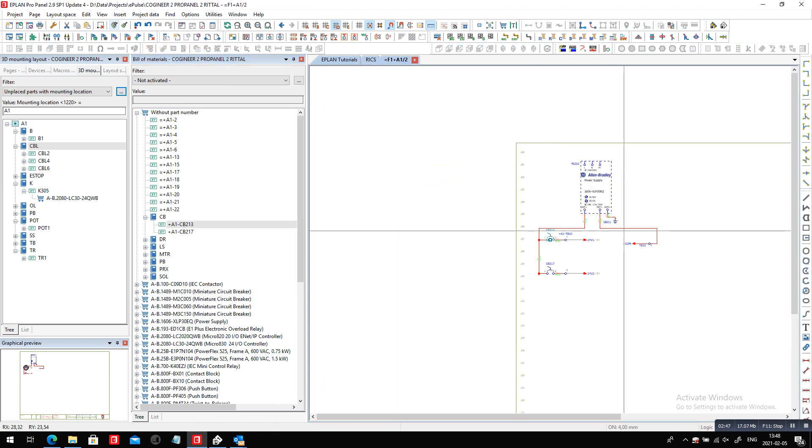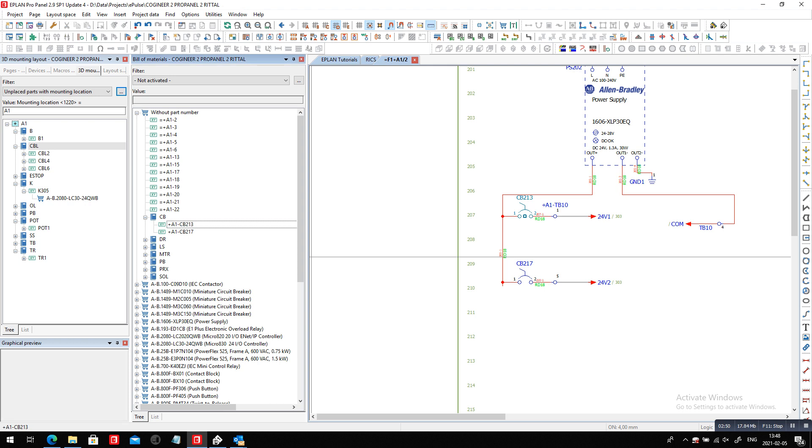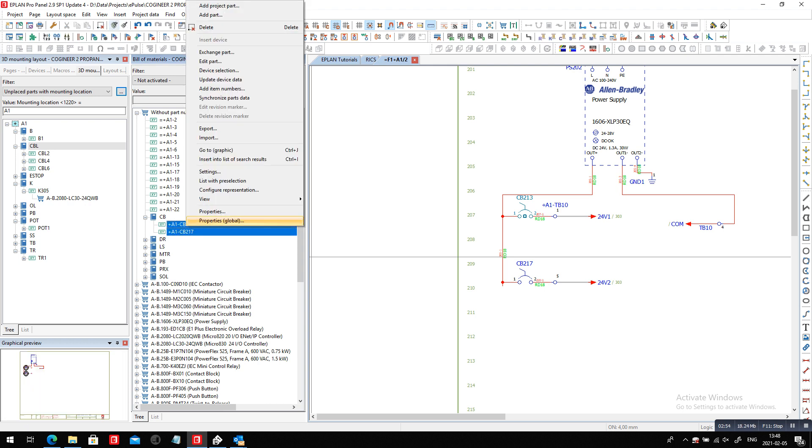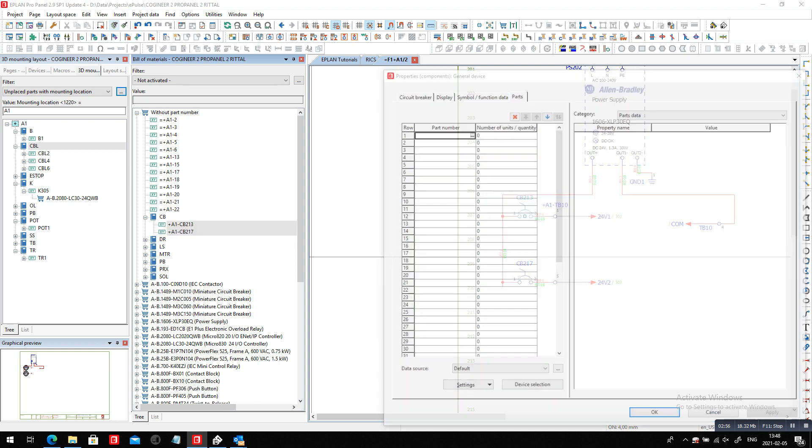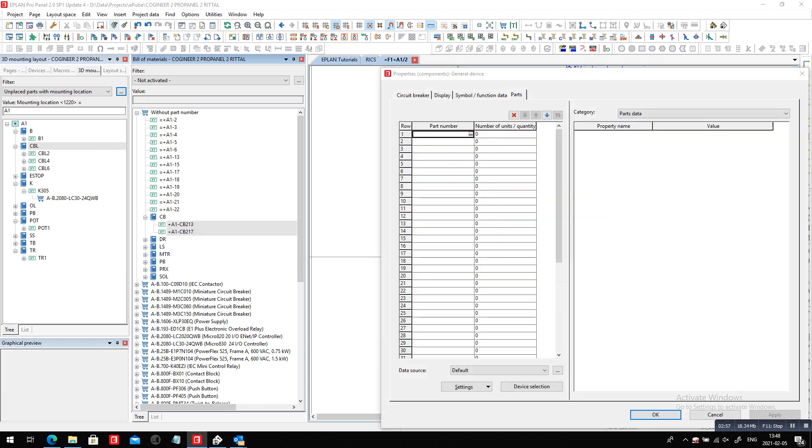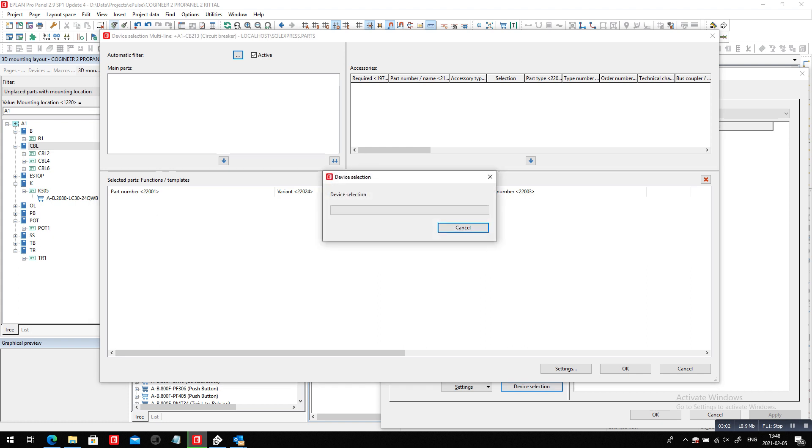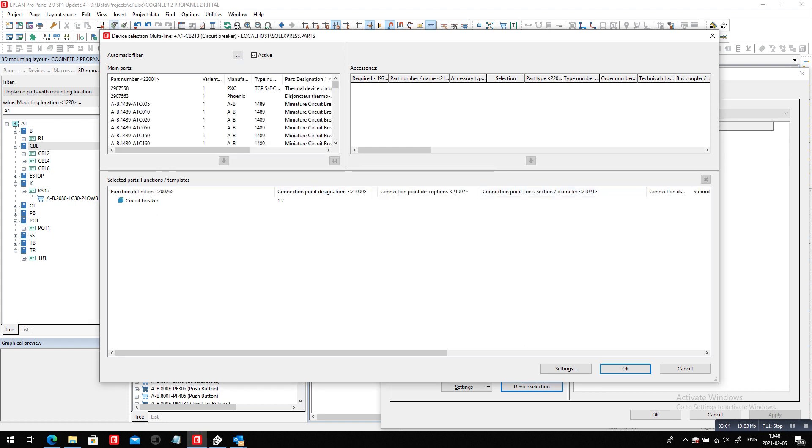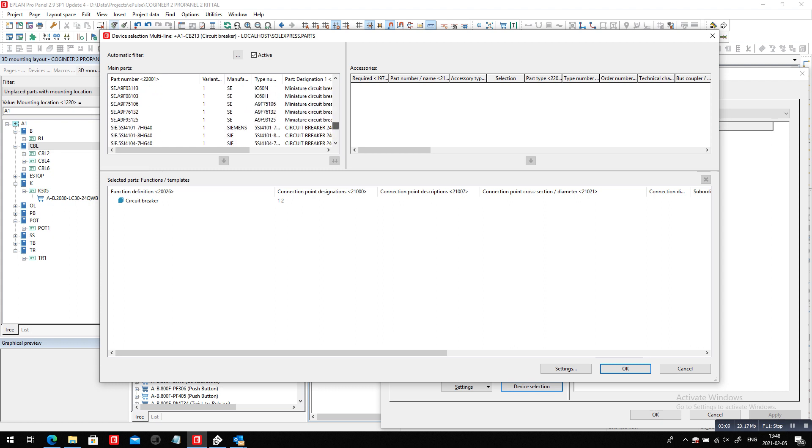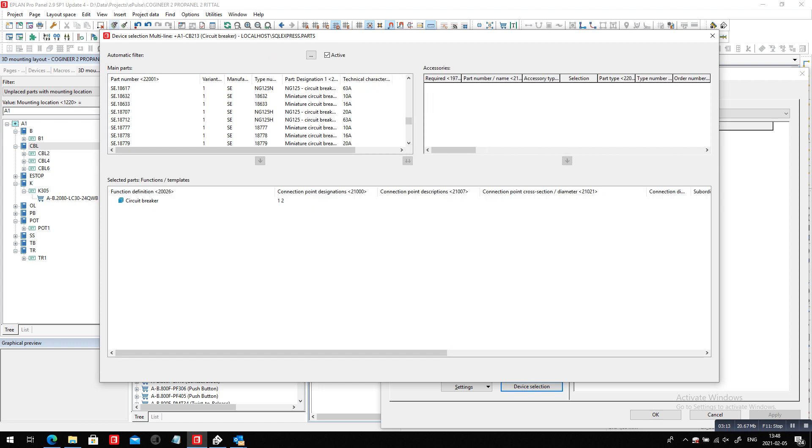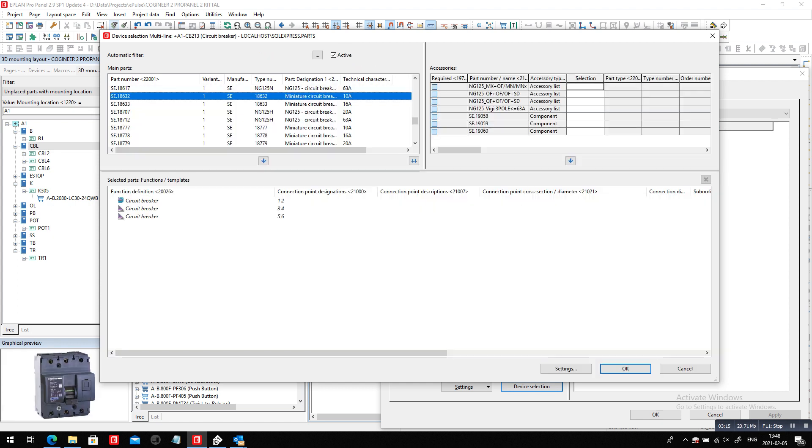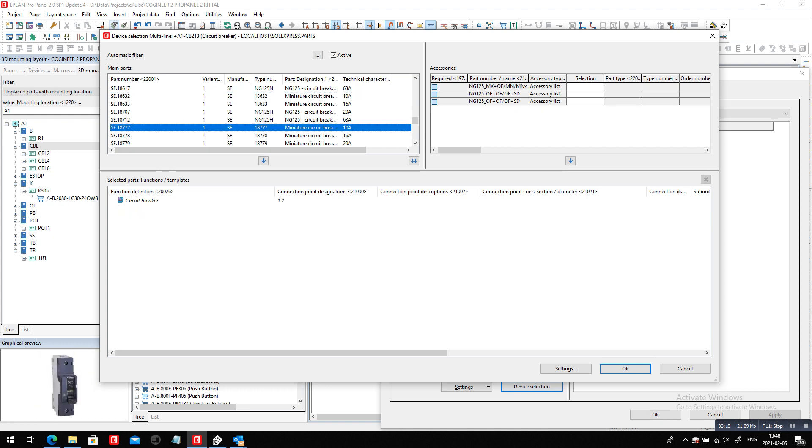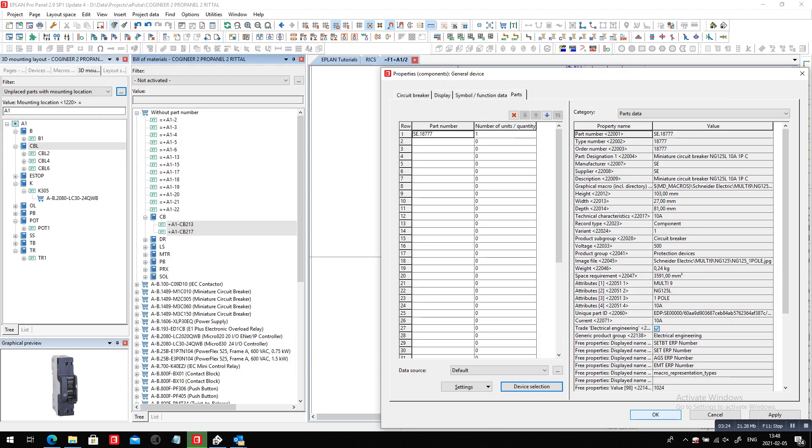So this means if I'm going back here to go to graphics, I can see I have here two circuit breakers that really have no part numbers yet. Of course, if you want to place these part numbers inside your panel, well, you might as well assign a part number. So here, let's go and check it out. What we have, we have Allen Bradley that could fit. We have some Schneider that could fit. We have some Siemens that could fit. So, of course, let's go with the description to be more precise. So these are very small one, 10 amps. That's a huge one. So maybe a small circuit breaker like this that could do it. And I'll just use this part number. So it's filled.